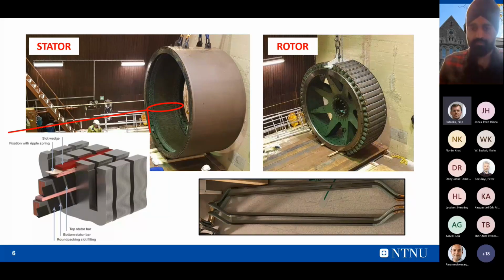Now at this point, this type of slots are there. These are the laminated steel core, and in each slot we have kept these windings. And the upper things are the wedges. If, with time, due to mechanical movement, these wedges loosen, they will start moving inside the slot and cause abrasion to the winding. So they are tightly packed inside the slot. There might even be a chance of discharges, because the core is at ground potential and the windings are at high potential. Because of abrasion the insulation also gets damaged, and that will ultimately lead to small discharges inside these slots also. That is called slot discharge.